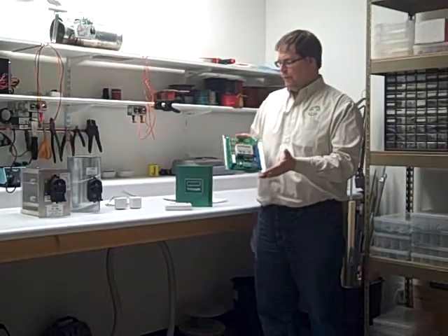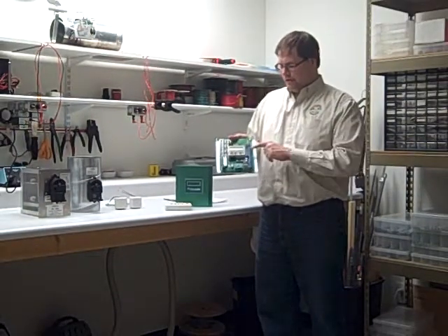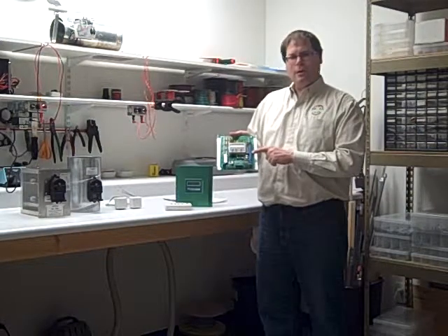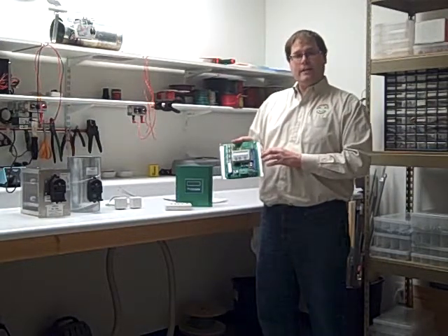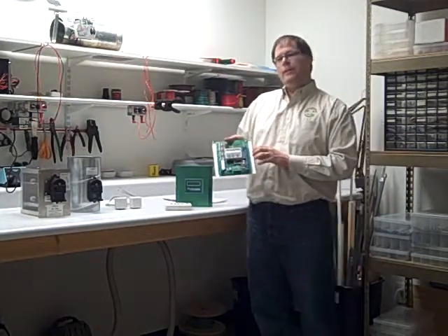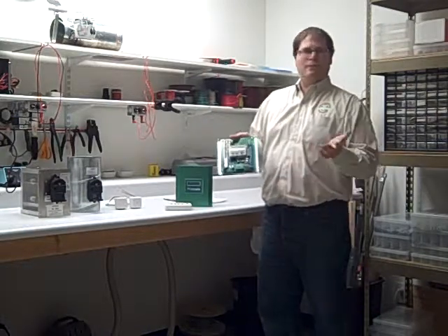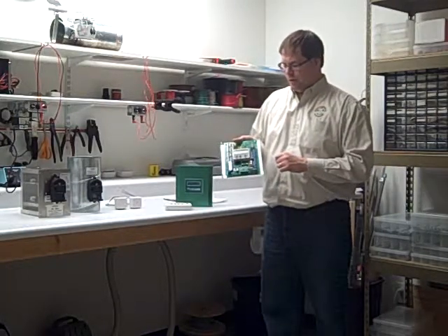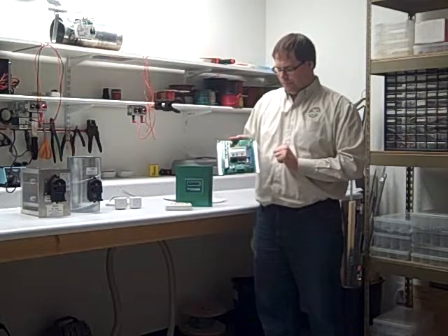There's no terminals for thermostats or dampers, so we just have terminals going to our equipment. We can actually do up to 4-stage heat, 2-stage cool, dual fuel heat pump, or single-stage heat cool. So no matter what type of equipment you've got, we're going to be able to control that.